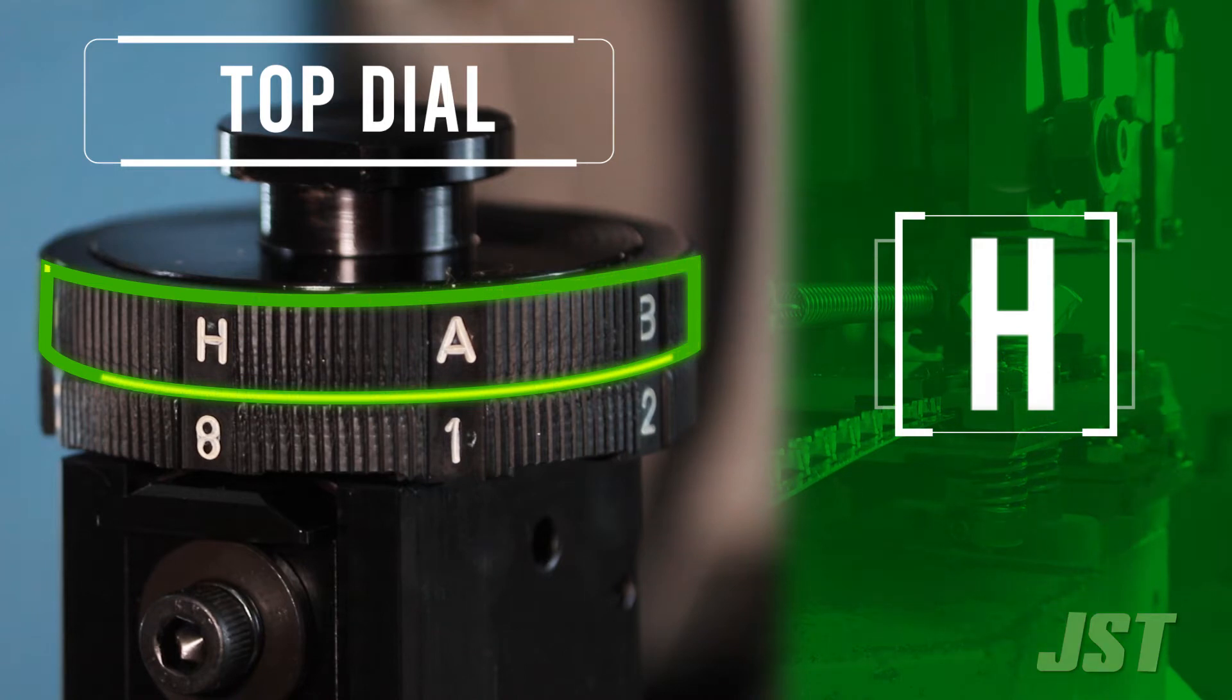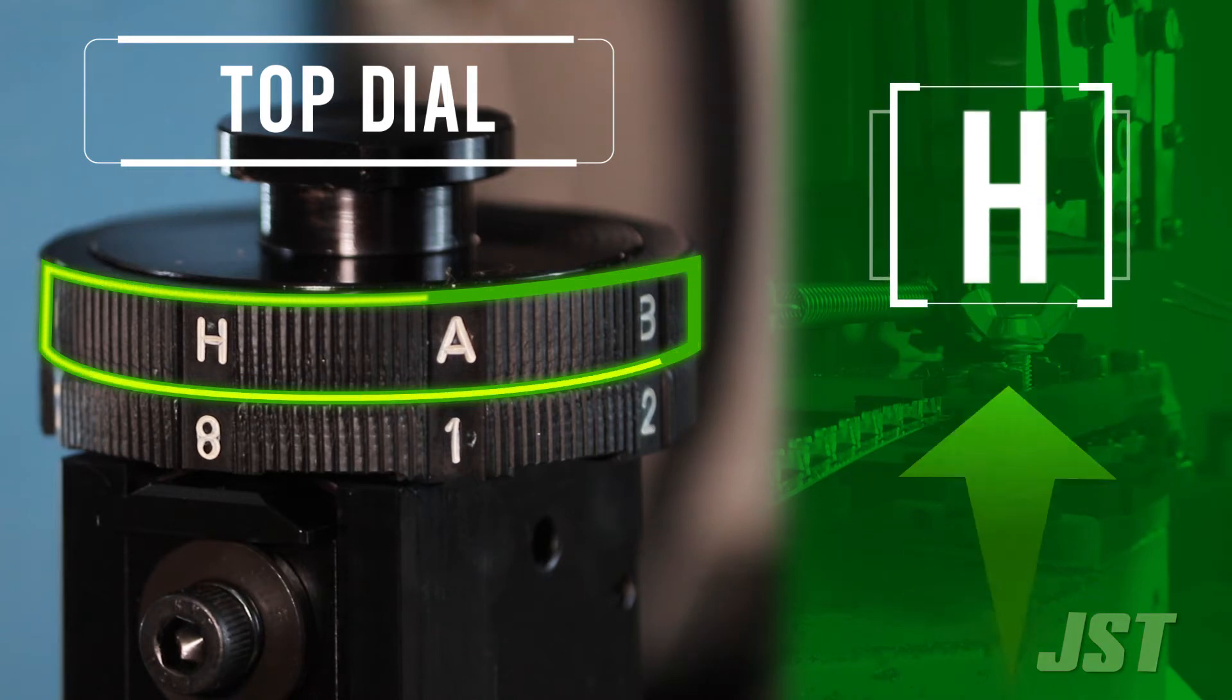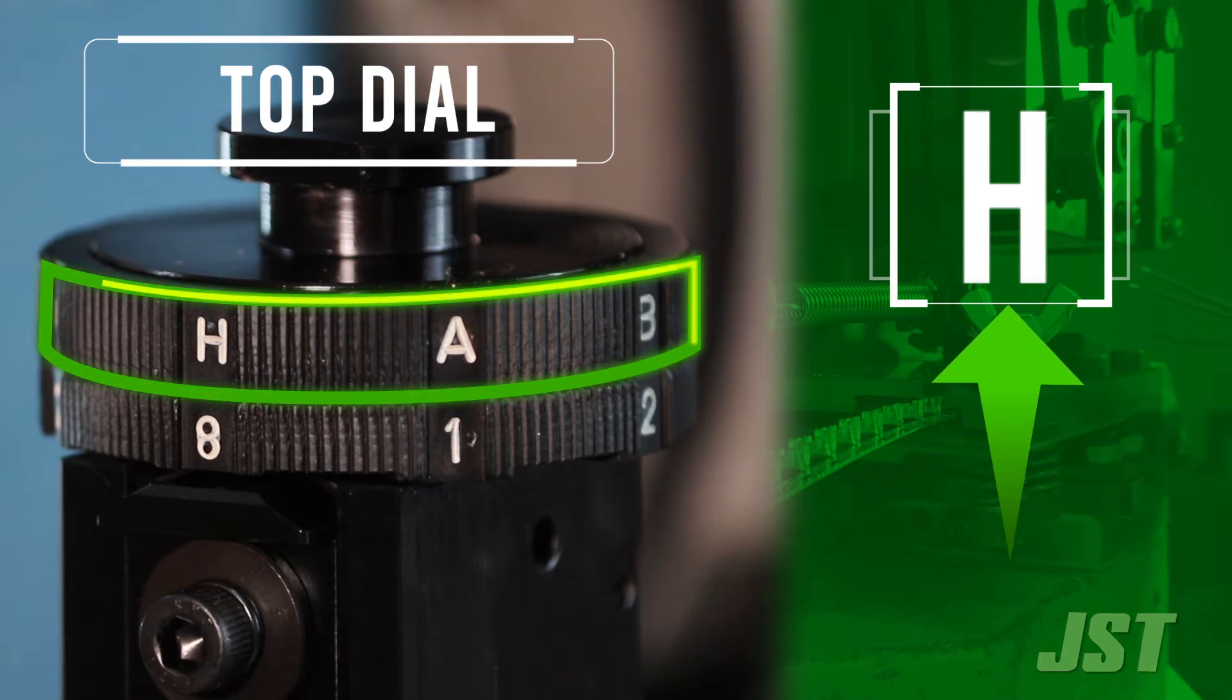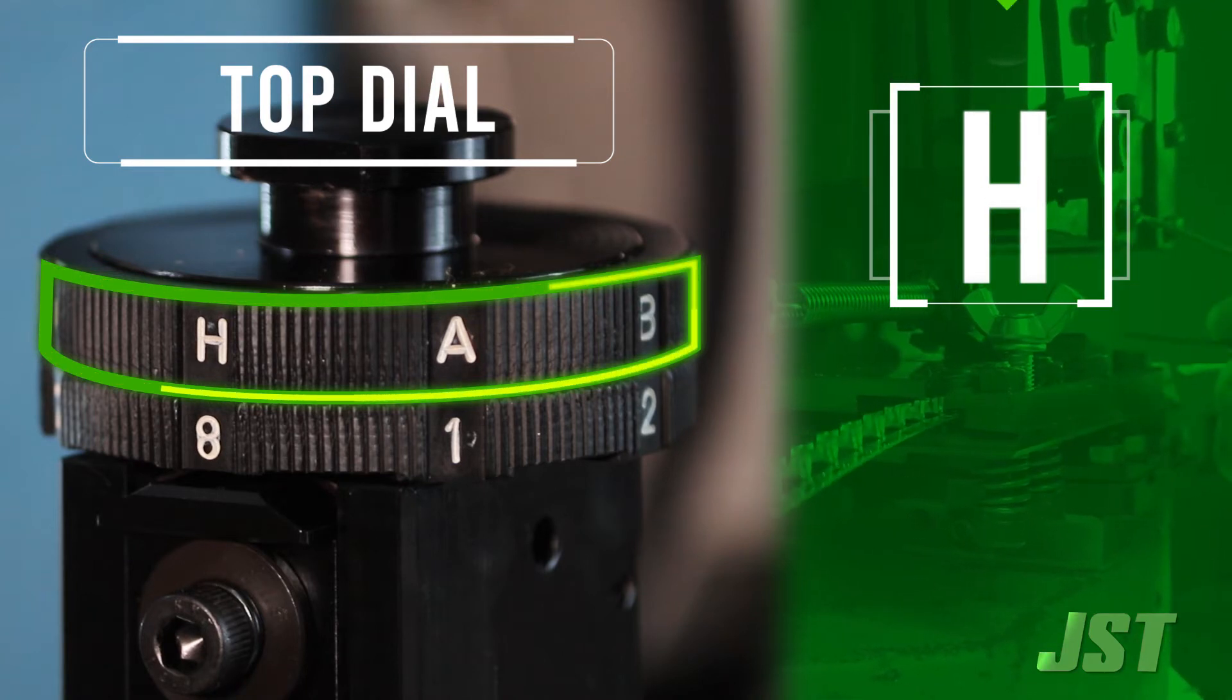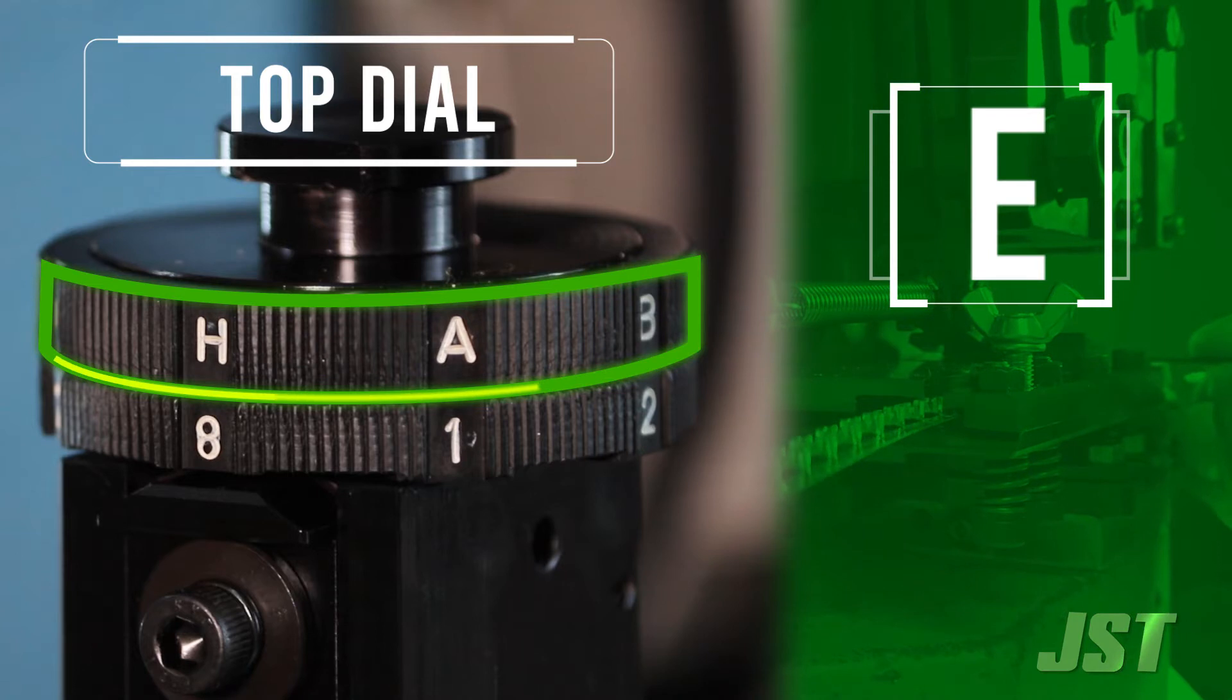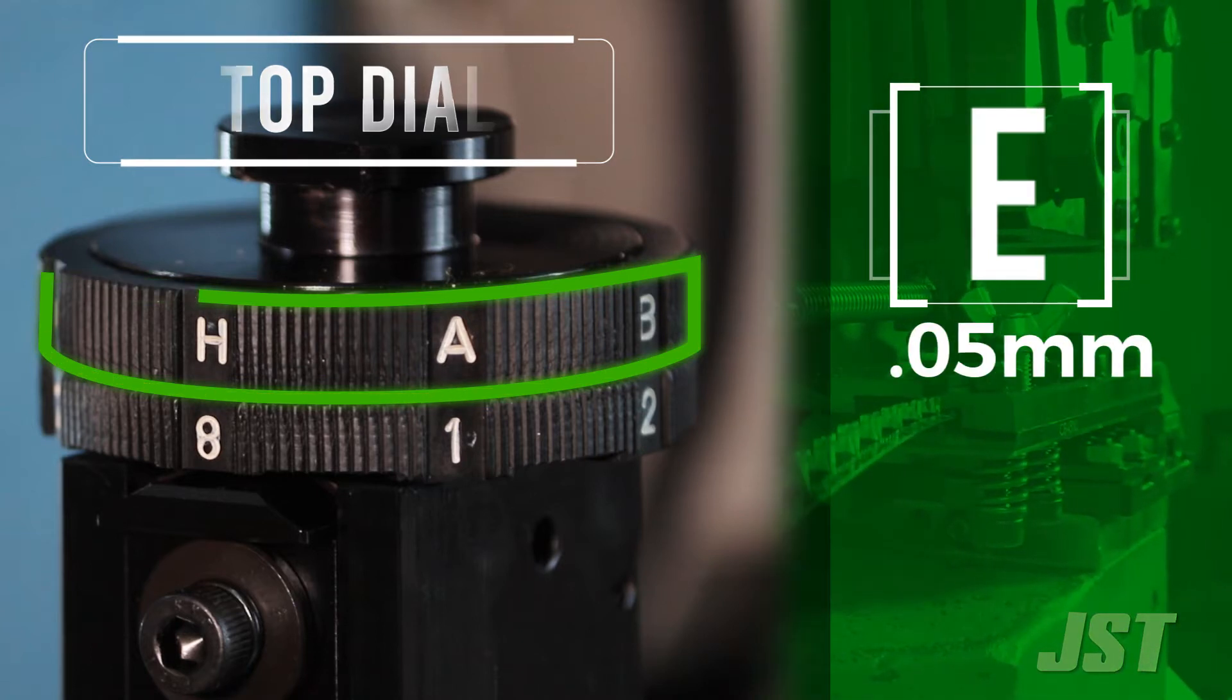H is the highest setting for the conductor and should always be the starting point. Each letter adjustment down changes the crimp height by 0.05 mm.